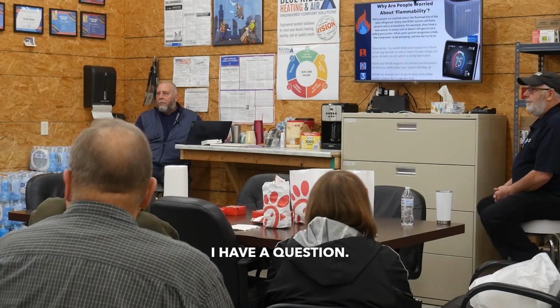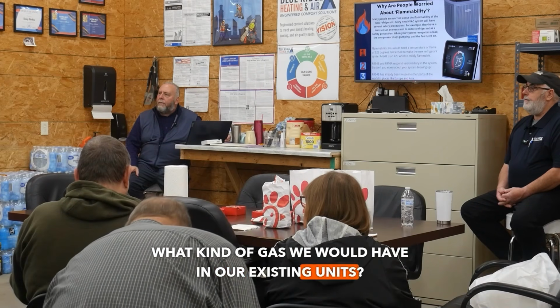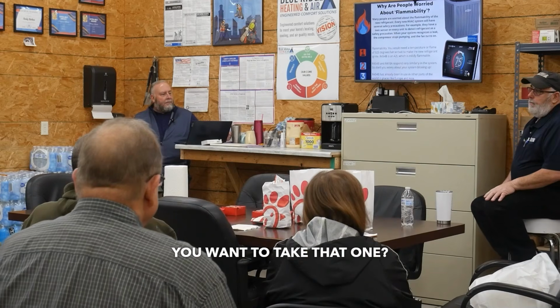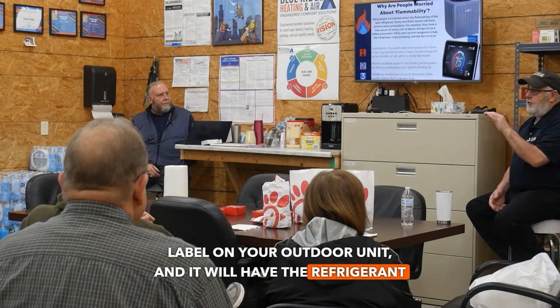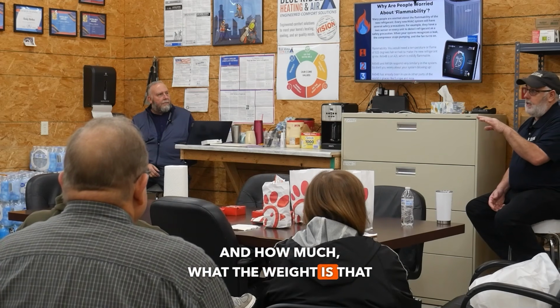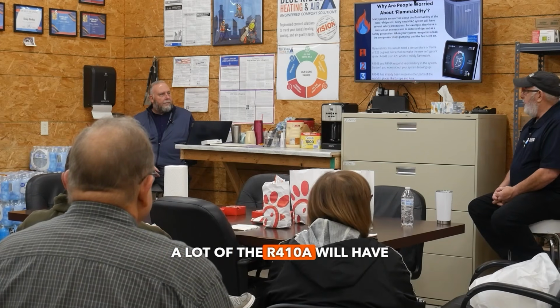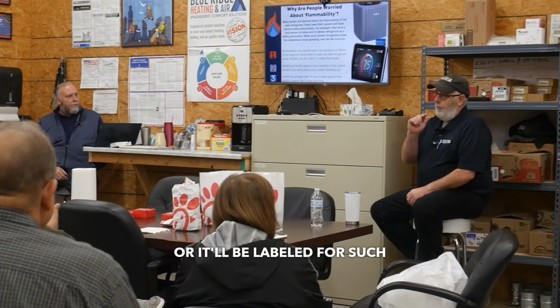Yeah, I have a question. How would we know what kind of gas we have in our existing units? So the question is, how would we know what kind of refrigerant is in your existing system now? Brian, you want to take that one? Most of you will have a label on your outdoor unit, and it will have the refrigerant and the weight that was installed from the factory. A lot of the 410A will have a pink sticker on there, or even on the indoor unit, you'll have a pink sticker, or it'll be labeled as such.